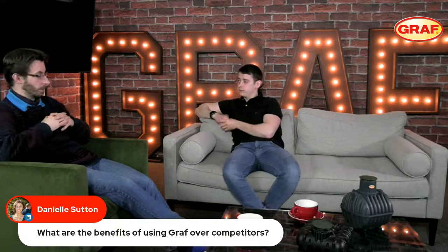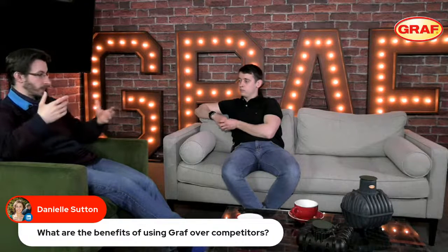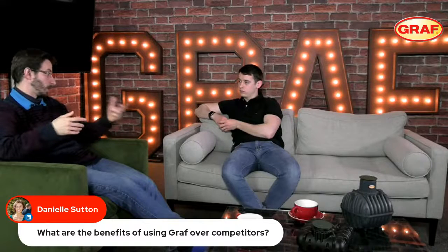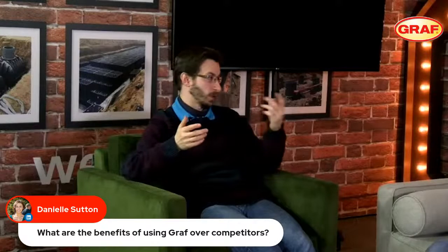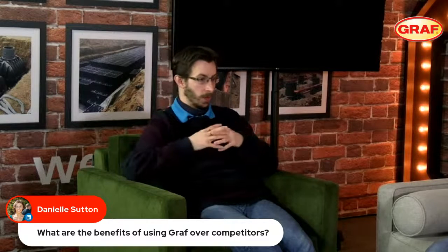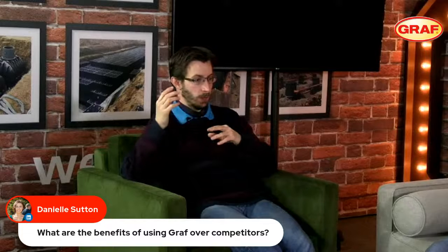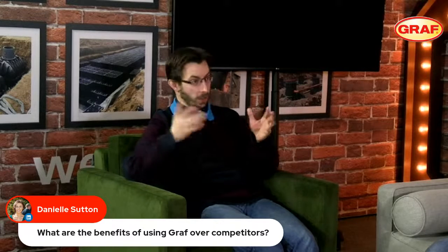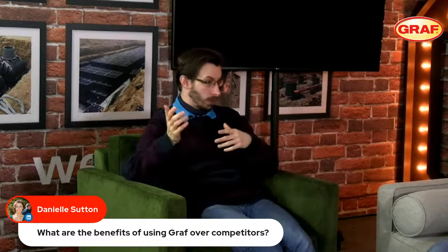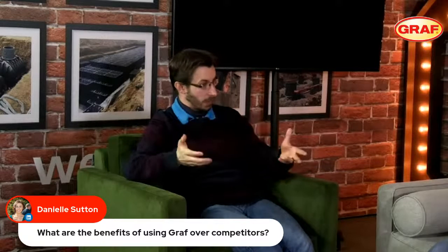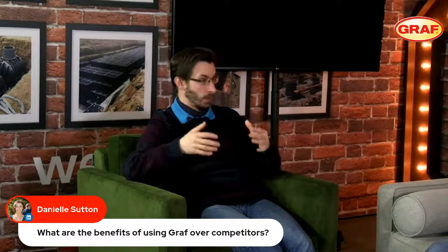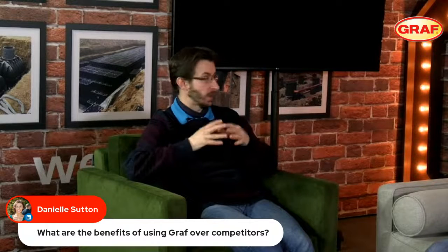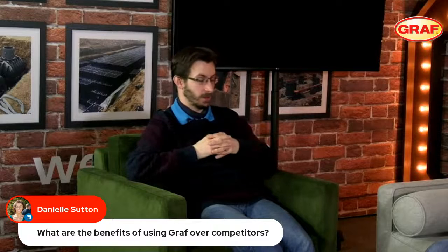Yes, this comes down very much to the type of plastic that is used within the system. You see different types of tank manufacturers. If you're talking old school, it could be concrete, but more commonly you would see glass reinforced plastic, which incorporates the concrete and backfill, as you say. With polyethylene tanks, generally we would recommend the use of gravel, which gives you a lot more flexibility during the installation, not having to get wet concrete or lean concrete mixed down onto the site, and not having to allow that to set. So with the gravel, you get a lot more flexibility in terms of your installation time for getting the tank into the ground.